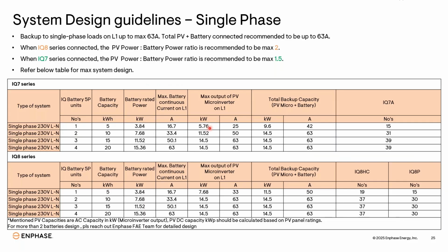DC you can overload. Like IQ7, the maximum output is IQ7A 366 VA, and you generally keep adding 540 watt panels there. So DC will always be more than this. The maximum panels allowed are 15 per phase. Same if you are using two batteries, 7.68 will be the rated output power. So 7.68 multiplied by 1.5 will be 11.52. So this will be PV plus micros is 14.5. We are not exceeding the 63 ampere limit.